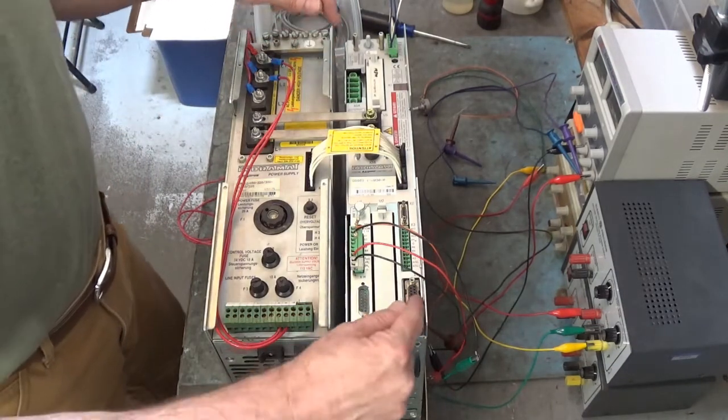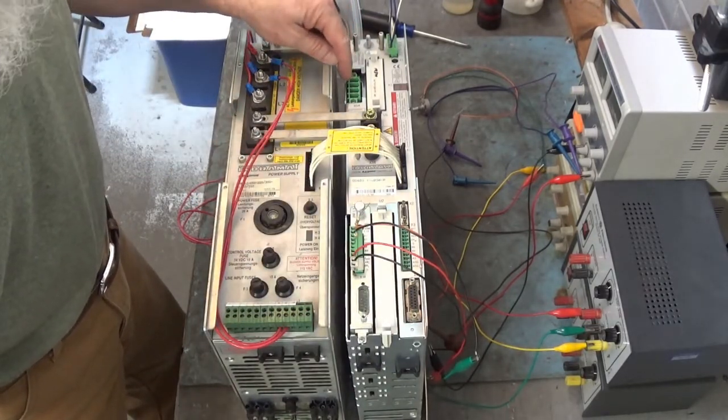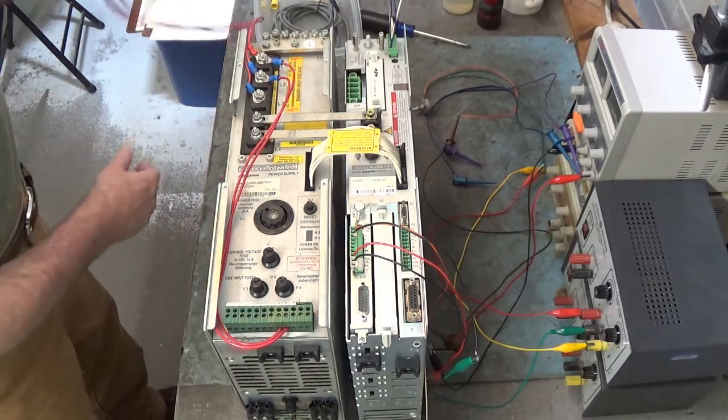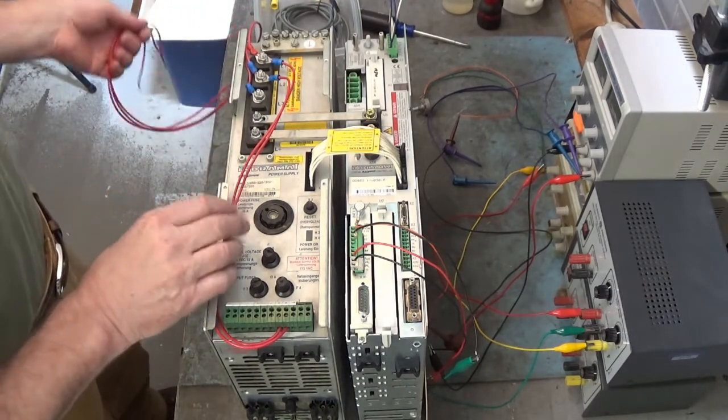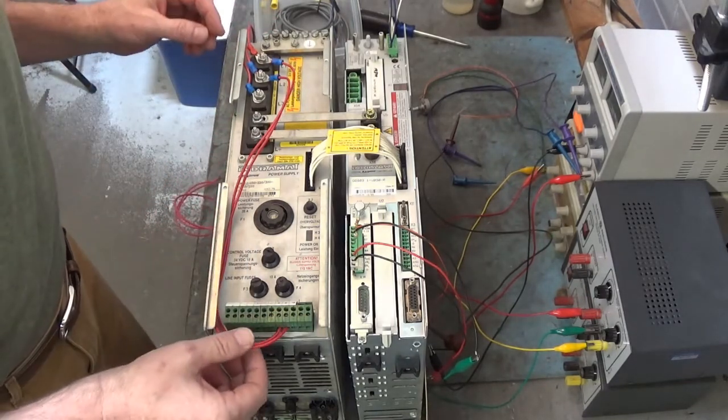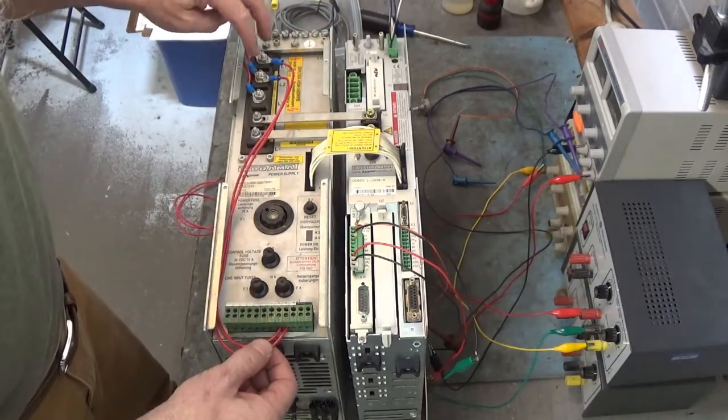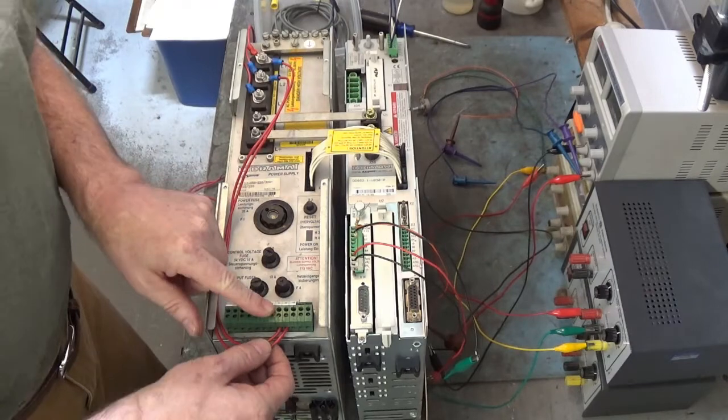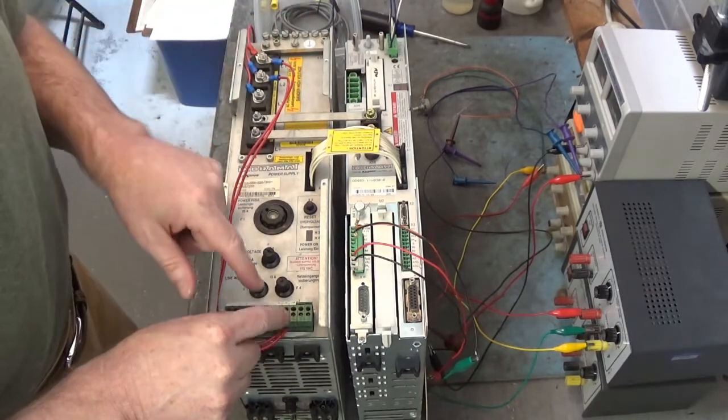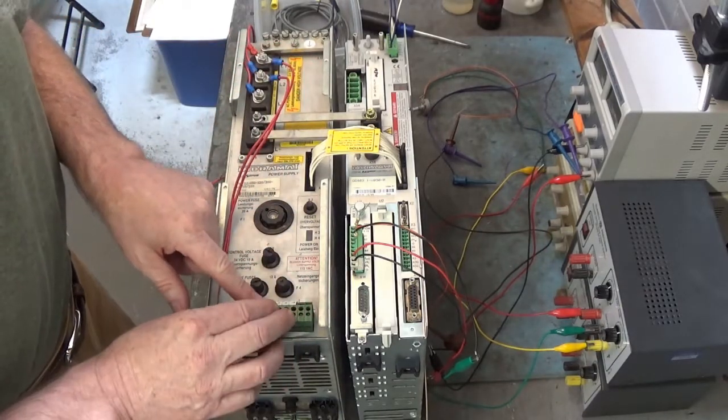We need to hook up the resolver to this connector from the servo motor. UV and W connect here. Then I've got to hook up L1, L2, and L3 to the bus power supply. That's 220 volts AC. You see we have two wires that come off of L1 and L2 that come down here to terminals 8 and 9. That power up the control voltages inside this bus power supply.